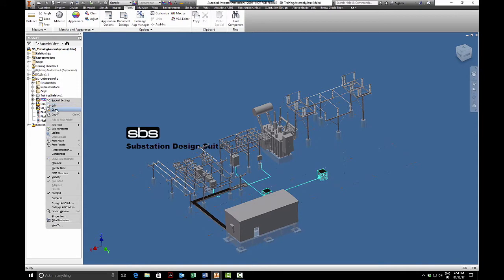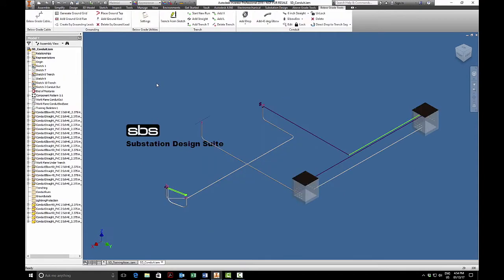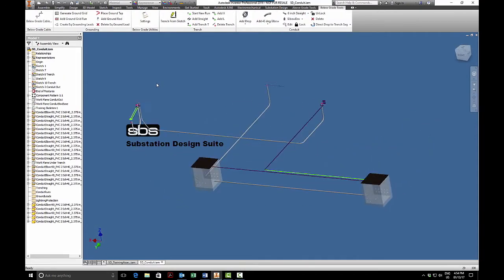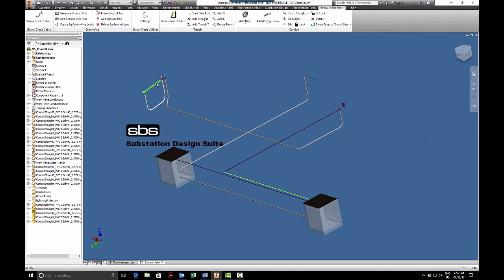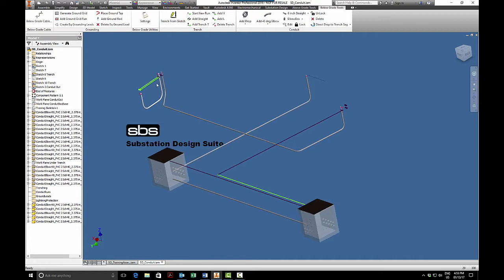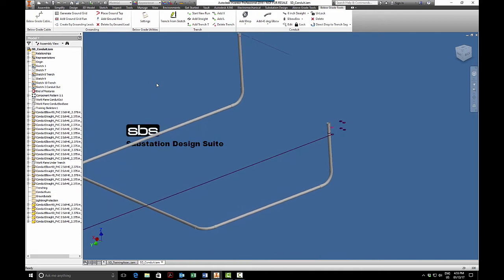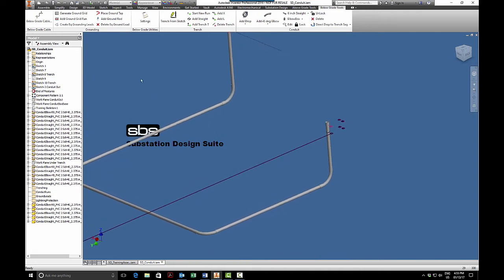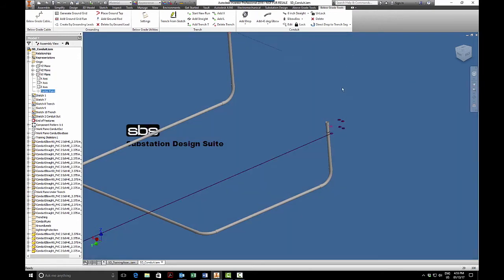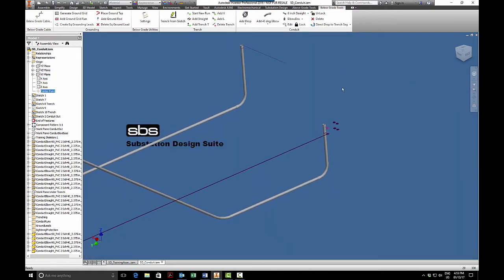I will open up my conduit and here we can see some sketches. Just like the trench we need a sketch, and just like the ground grid we need a sketch to run our conduit. You can see I have my main sketch, sketch one is identified on the XY plane, and the XY plane in this case is top of concrete. It could be your zero zero reference or however you wish to have it.